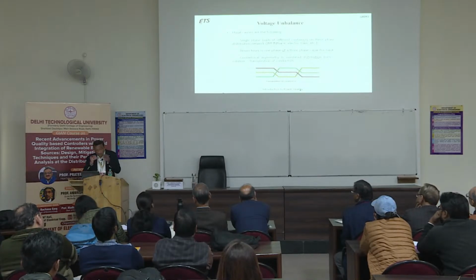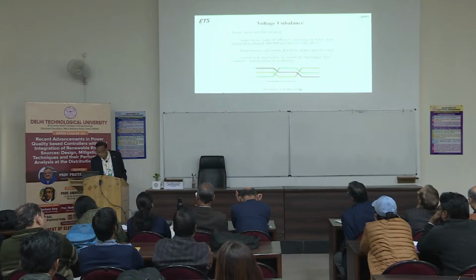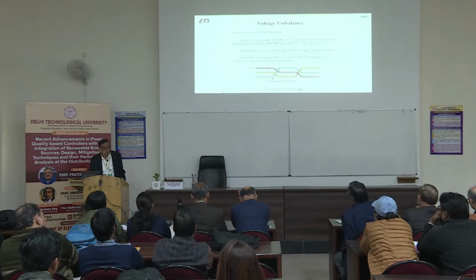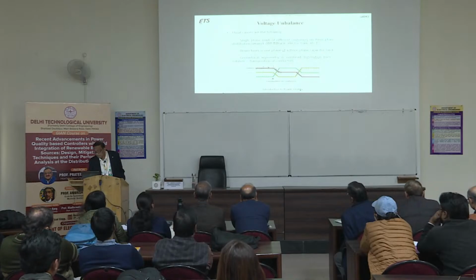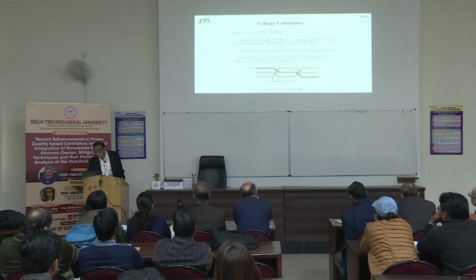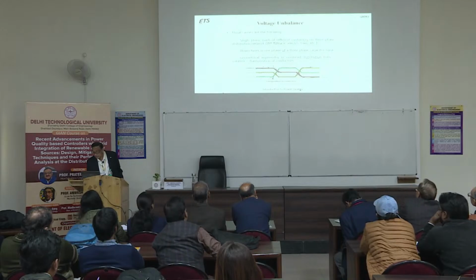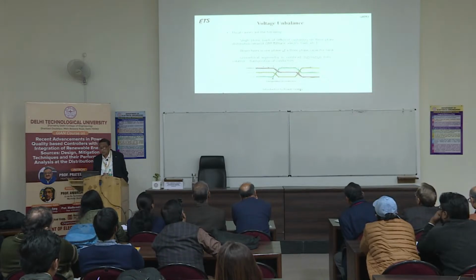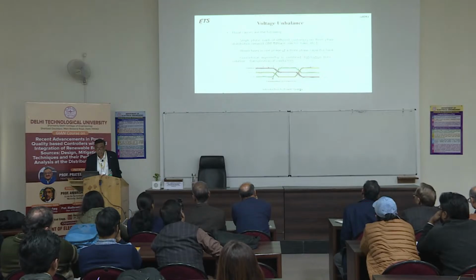So how to correct it? This is nothing new. It is the transposition of conductors that we do. Like position of phase A, after a few kilometers you change the position of phase A, and again after a few kilometers, similarly phase B, after a few kilometers you physically change the position of the conductor like this. For C, you can see. So this is called the transposition of conductors, which is normally used almost everywhere.